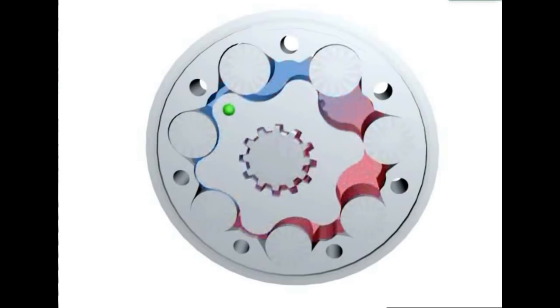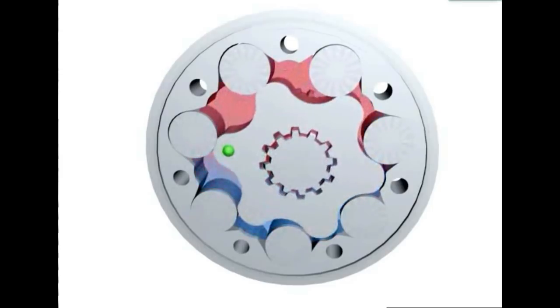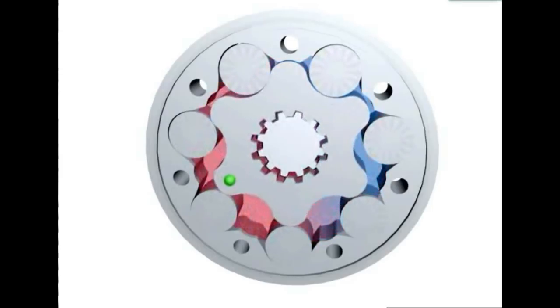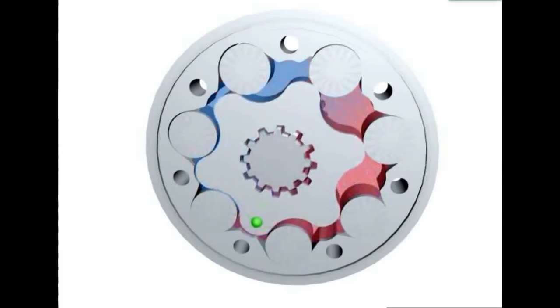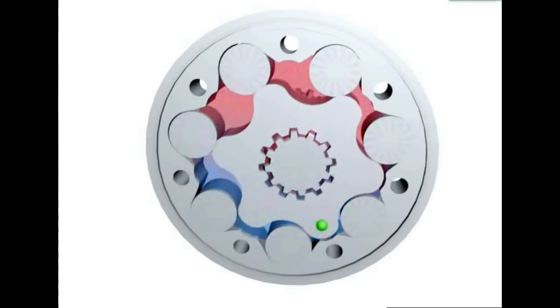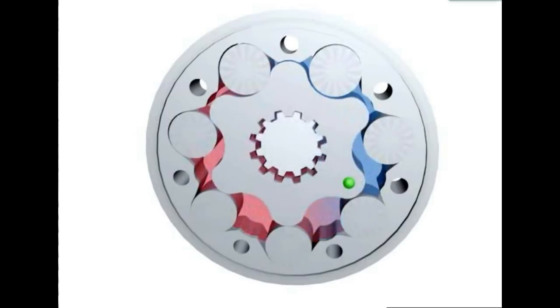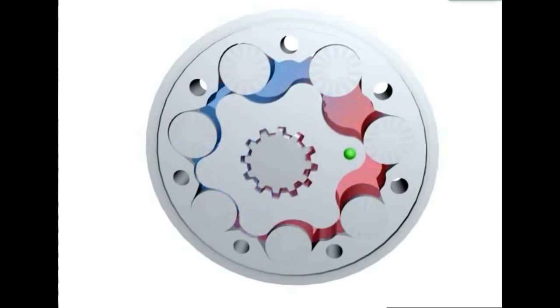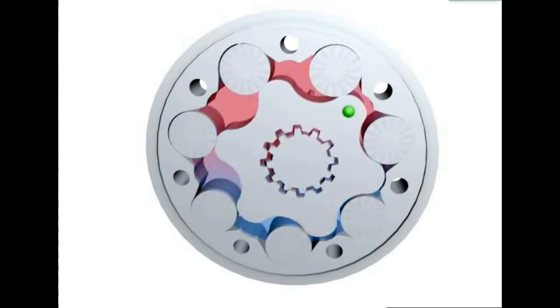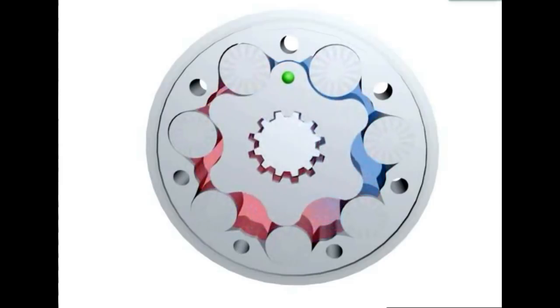For each orbit the rotor makes, the rotor rotates one tooth in relation to the stator. Since this stator has 7 roller teeth, it takes 7 orbits of the rotor to complete one rotation of the output shaft. This creates a 7-to-1 speed reduction and a similar multiplication of the torque output.